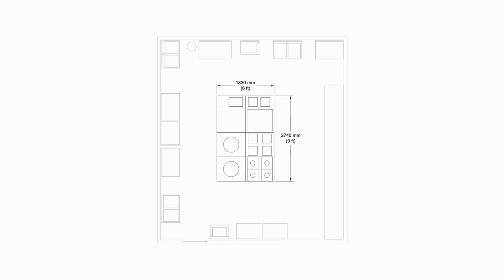To calculate the required exhaust flow rate, we need to know the kitchen hood length. This is usually provided by the kitchen specialist, but if we don't have it, we can estimate it by adding 1 foot to all sides of the kitchen block. This 1 foot is known as overhang, meaning the kitchen hood extends 1 foot out of the cooking equipment. By doing so, our kitchen hood length is 11 feet.